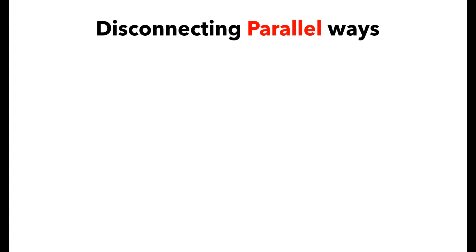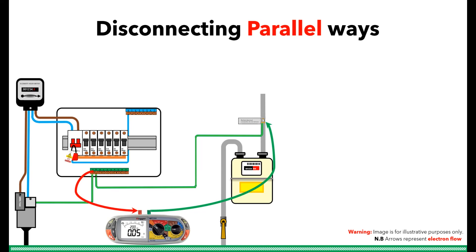We often hear the term parallel ways, but what does that actually mean? This diagram represents what would happen if you were testing a main bonding conductor between the main earth terminal, or MET, and the gas pipe if there was nothing else connected. The electrons would flow out of the negative terminal of the MFT along the test lead through the main bonding conductor and into the MET before traveling back into the positive terminal of the batteries within the MFT and completing the circuit.